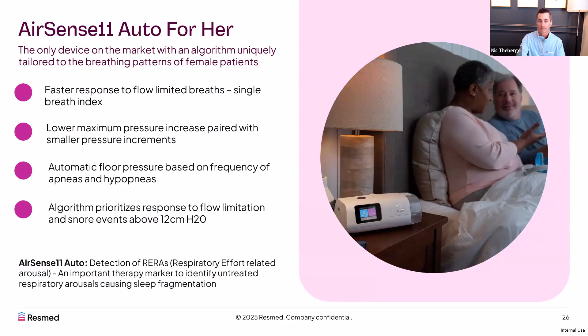Also important to note that all the devices will detect and give you a marker for residual events, but also residual RERAs, so respiratory effort-related arousals. And that's really important to give us an indication that the mode should be changed from a standard auto to an Auto for Her. Basically, it's giving us the marker that, hey, this algorithm is missing these flow limited events, and we're going to give you that marker in the report to say, if we change it now from the standard to the Auto for Her, we know that all those events will be treated. As a result, the For Her algorithm will respond sooner, but with a gentler pressure increase, right? And that's the important thing to highlight: with the single breath index, the device can do things more effectively.